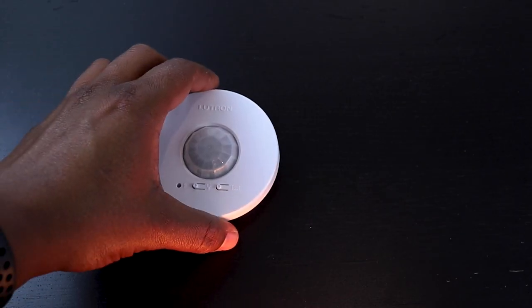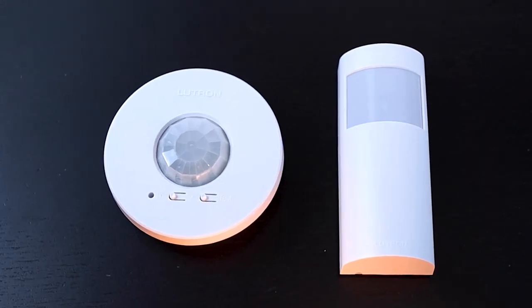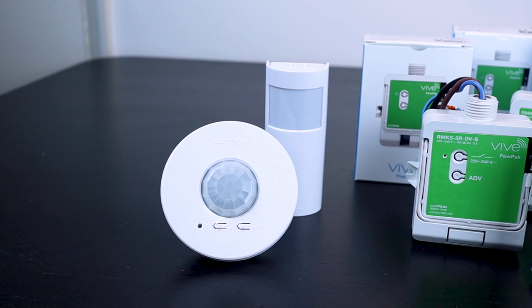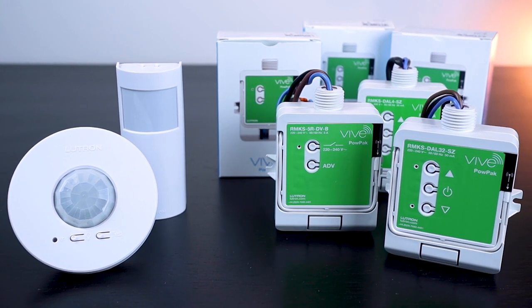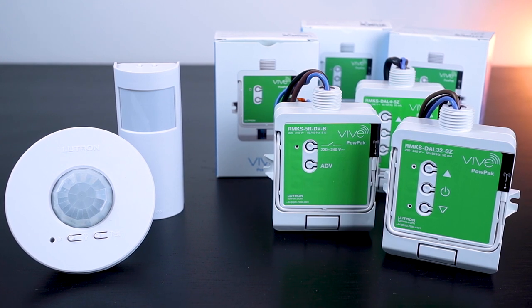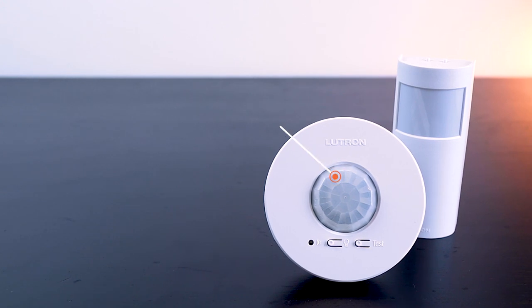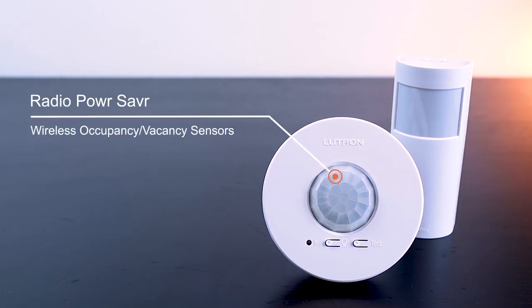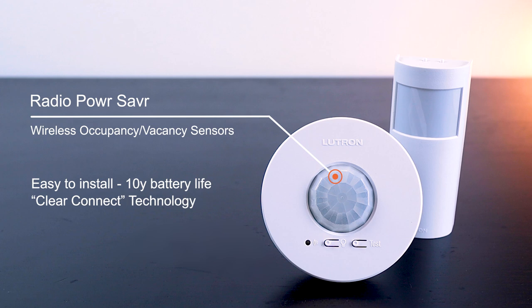Lutron offers a full range of wireless occupancy sensors called Radio Power Saver that can be used in different types of installation. All those sensors are part of the Lutron Vive Solution and therefore they can be used to control Lutron PowPak Wireless Lighting Modules. They are all passive infrared wireless sensors, so they are all very easy to install with a battery that can last up to 10 years.